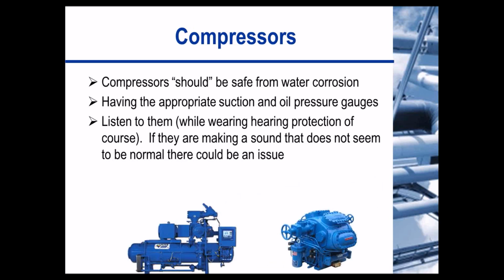Compressors should be safe from water corrosion, but having the appropriate suction and oil pressure gauges is something that we've seen could be an issue. Another thing you may want to consider is listening to them and being aware of how they typically operate and how they sound. This is one thing where just being attentive can really help avoid any serious issues.